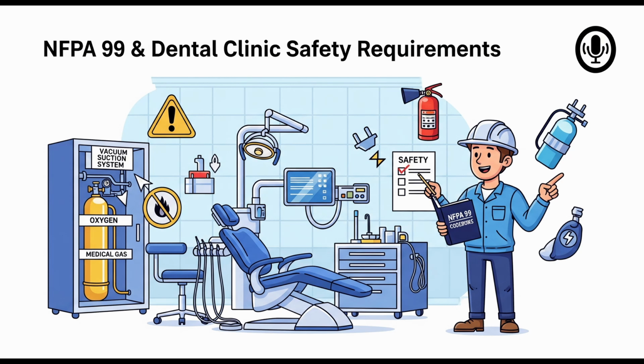This panel can combine the functions of a master alarm, monitoring the source equipment, and area alarms, monitoring pressure in specific zones. One panel for everything. Where does it have to be? It has to be located in an area of continuous surveillance whenever the facility is operating. So think maybe the main reception desk or a central station where staff are always present during patient hours. It can't be tucked away in a closet somewhere. Makes sense. You need someone to actually see it.